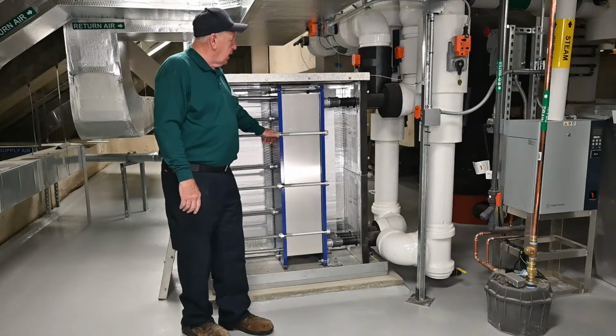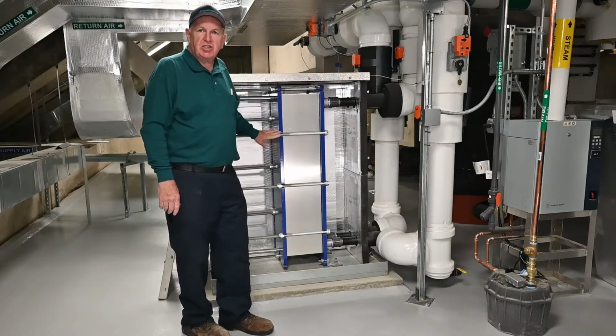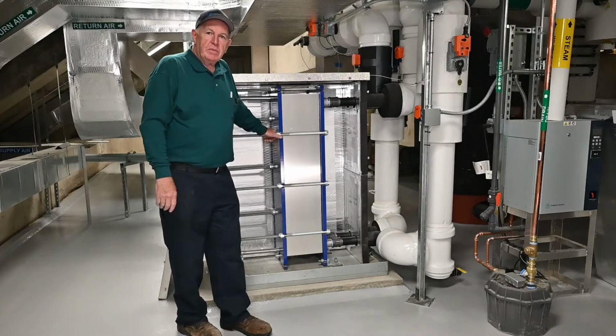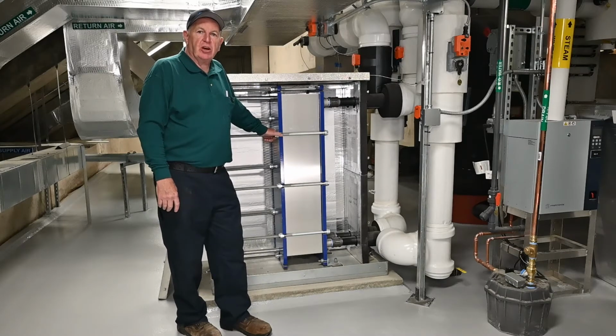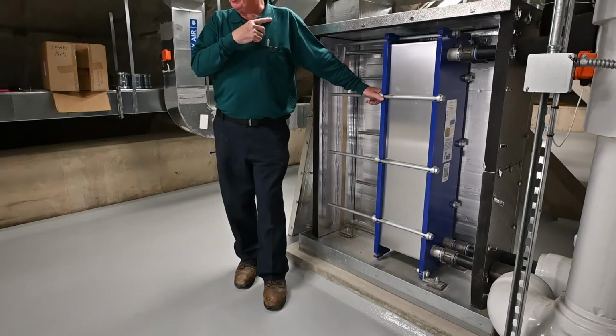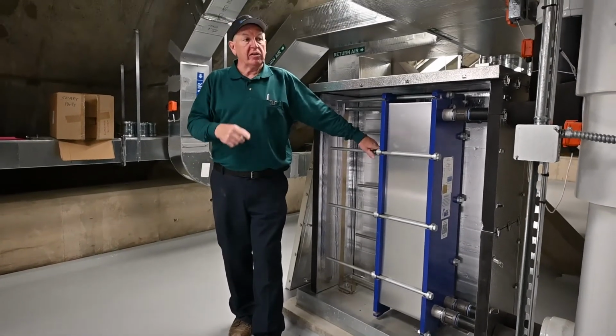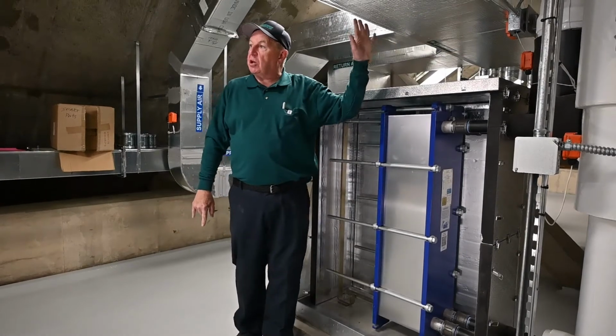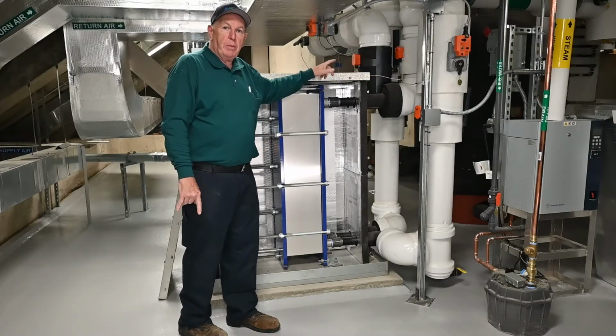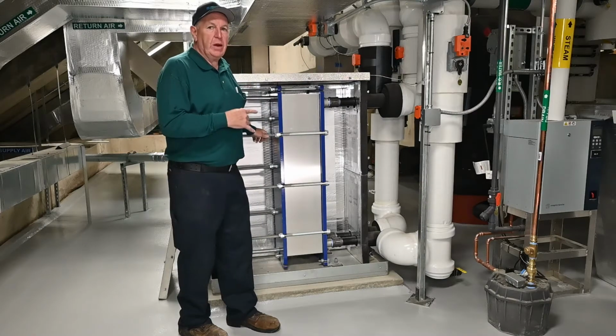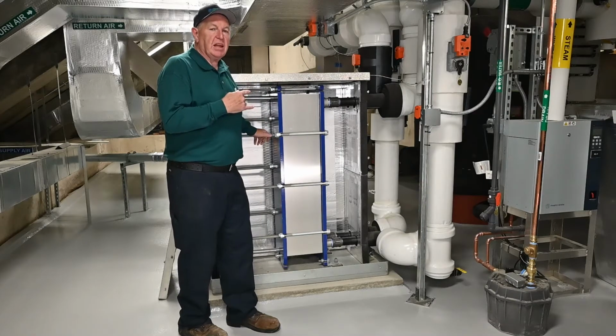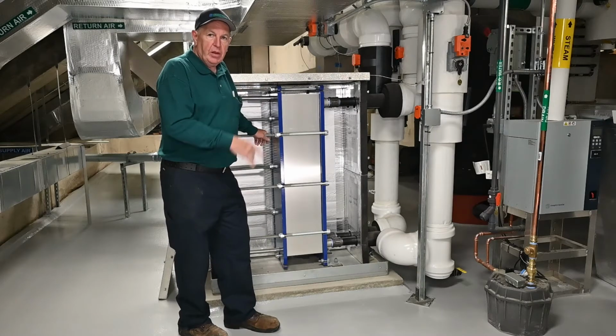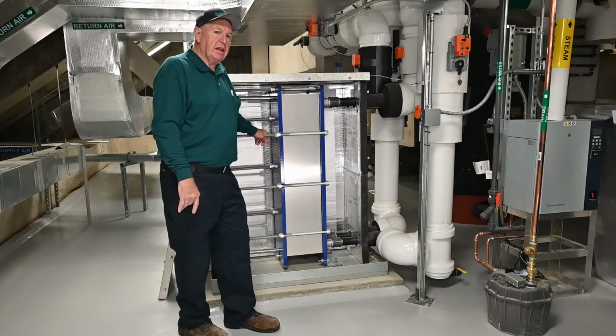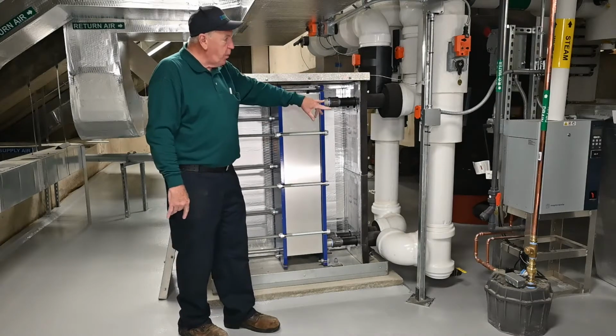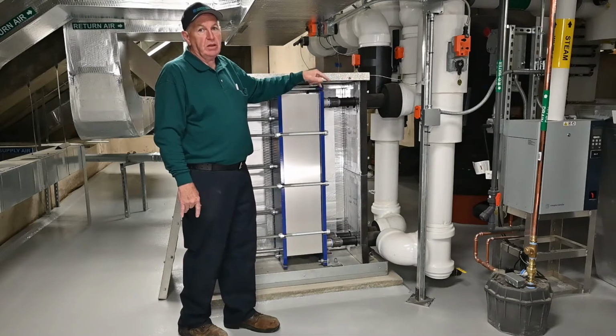heating project, and this is a heat exchanger that uses the building chiller if for some reason the chiller that's dedicated to Rare Books is inoperable. They can swap it over automatically by opening these valves, and they'll take the building chilled water to chill the Rare Books air handler. This is only a backup. Typically, the chiller that's dedicated to Rare Books will serve the air handler. And this is only if the chiller is inoperable, these valves will open, and they'll use building chilled water to do the same thing the chiller does here.